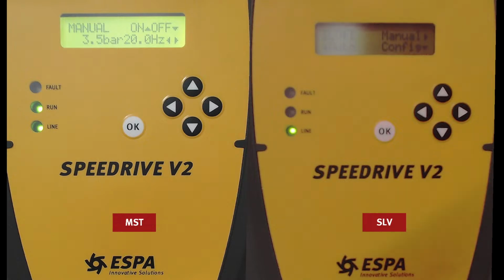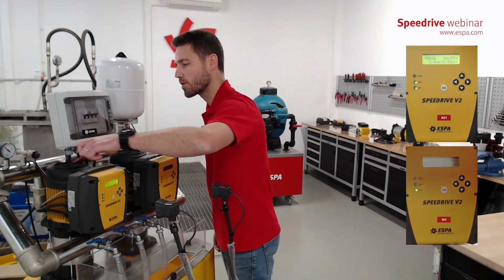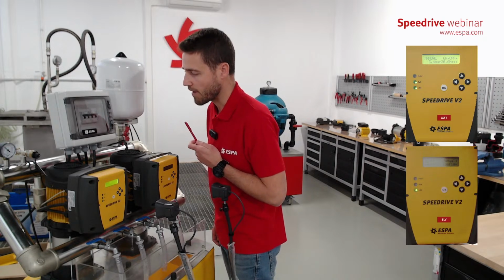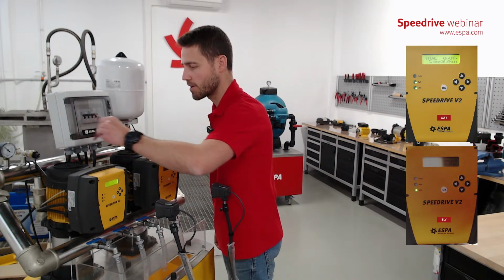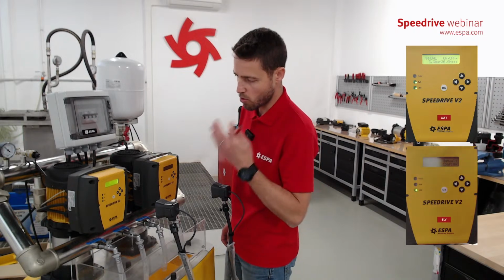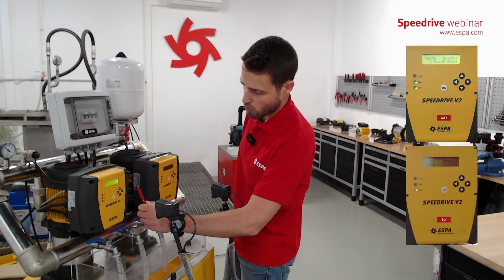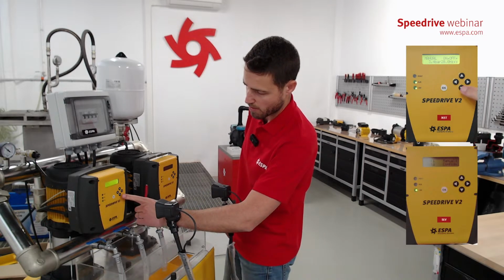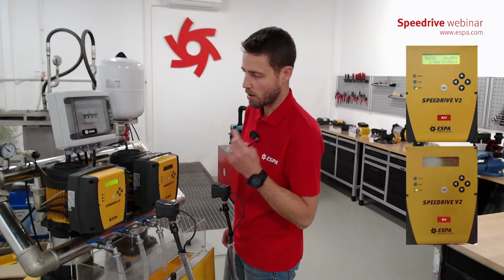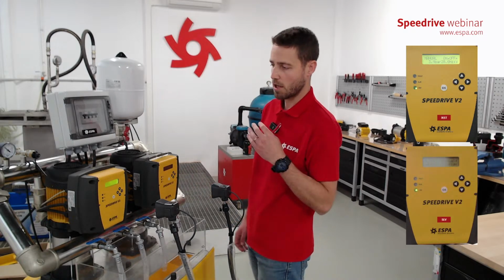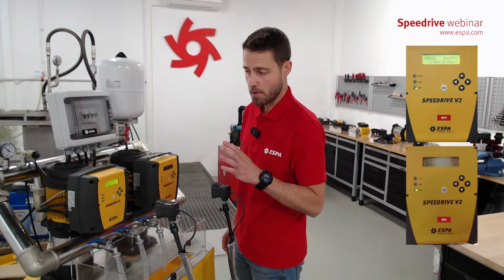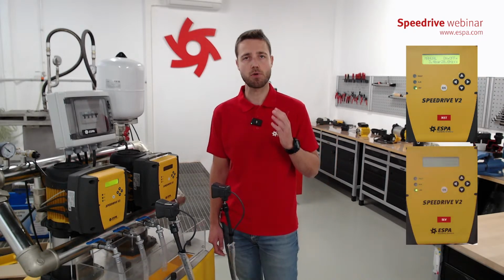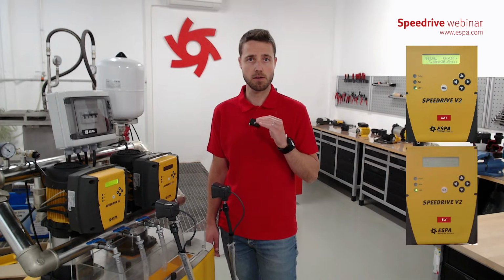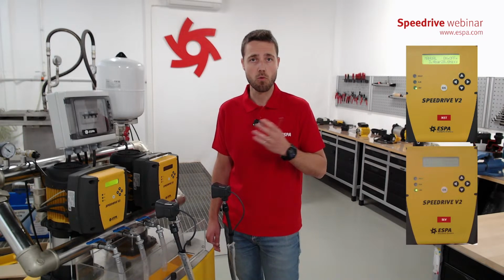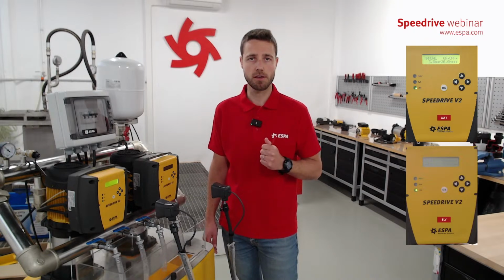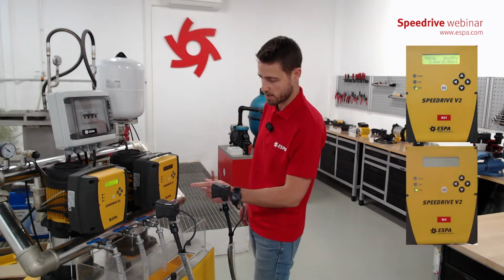Now the pump has started. We have to go over to the pump and have a look at the fan. Now the fan is turning clockwise, so the motor is turning properly. We have finished this part, and we can turn off the pump. If it turns the other way around, the pump will work, but it will not give the pressure that we desire. For example, if the duty point is 3.5, maybe the pump will work at 1 or 2 bars. It will not give more pressure because it's turning anti-clockwise.